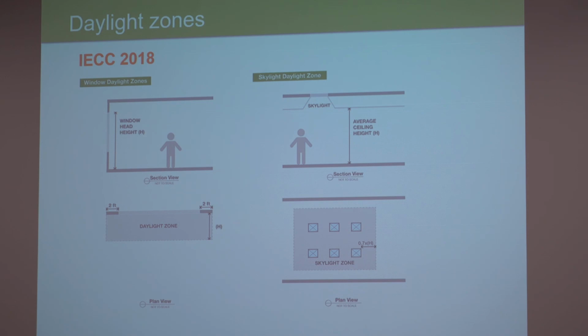So what is a daylight zone? This is how IECC defines it, and it's similar in ASHRAE and in California. It's one window head height, so that's the top of the window to the floor, one window head height into the space, and then 2 feet on each side of the window. That's the side light daylight zone. And then for skylights, it's basically the area of the skylight, and then 70% of the ceiling height all the way around the skylight.